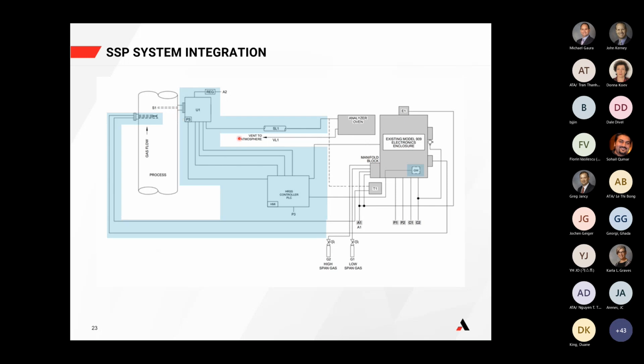The other thing that we want to point out is the reason why we suggest you replace the sample line: there's a good probability that your sample line was not designed to run at a maximum temperature of 190 degrees C. That's the biggest requirement why we would suggest that it be done. If the sample line was designed for that specification, then you could probably get away with it. But to be honest, if you're going to spend the amount of time and effort in putting something like this together, we would suggest you replace the sample line as well.